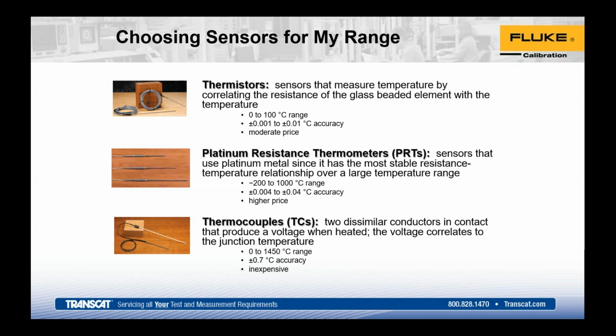The next jump down are your more typical RTDs or PRTs, where you see the more traditional sheath lengths. These tend to have higher accuracy, slightly higher cost, but again a variety there. The most common ones, more industrial, are your 100 ohm RTD, or a DIN class A RTD, or a 385 RTD or 392. These are all just references to the types of platinum used, their curve fit, whether it's generic or very specific - so it's about getting familiar with what you're calibrating.